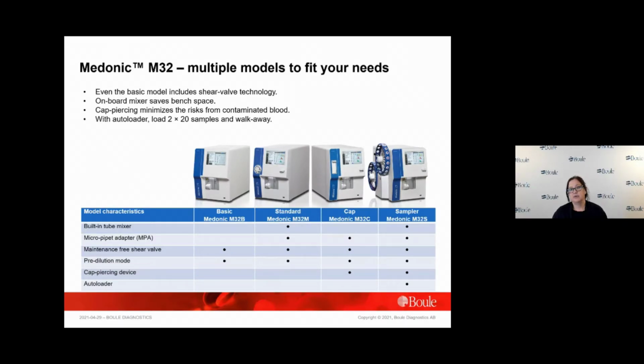The system is available in 4 models that fit various clinical needs. All models include the closed shear valve. Standard, cap, and sampler models are all equipped with MPA module. The cap and sampler models are also equipped with a cap piercing device for sample aspiration from closed tubes to protect the operator from possibly infectious samples. And the sampler model provides a walk-away solution for 20 samples. Both the standard and sampler models have built-in mixers.